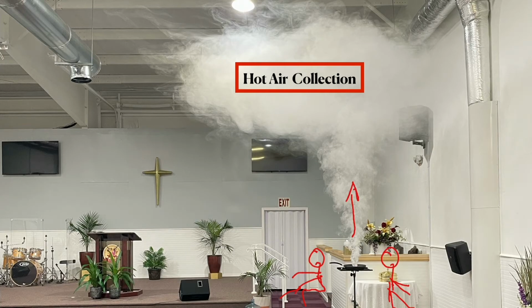And you can already see this 40-second bomb before it has finished burning. You can already see the plume is lopsided, right? It's more on this side of the plume over here, because you can see the effect of this nozzle here is starting to pull the smoke already. You can see the effect of that already. So what we want to see is this smoke now gets pulled over into the collection manifold.